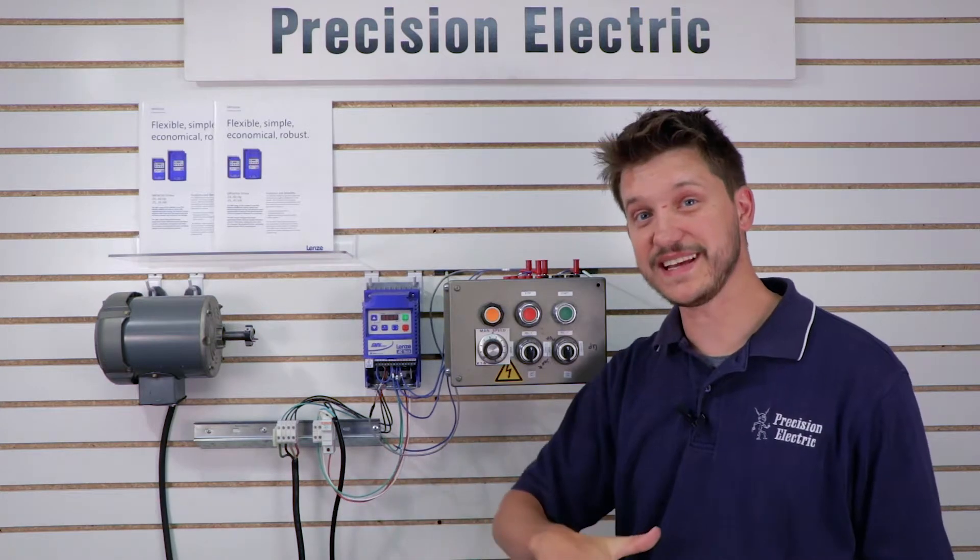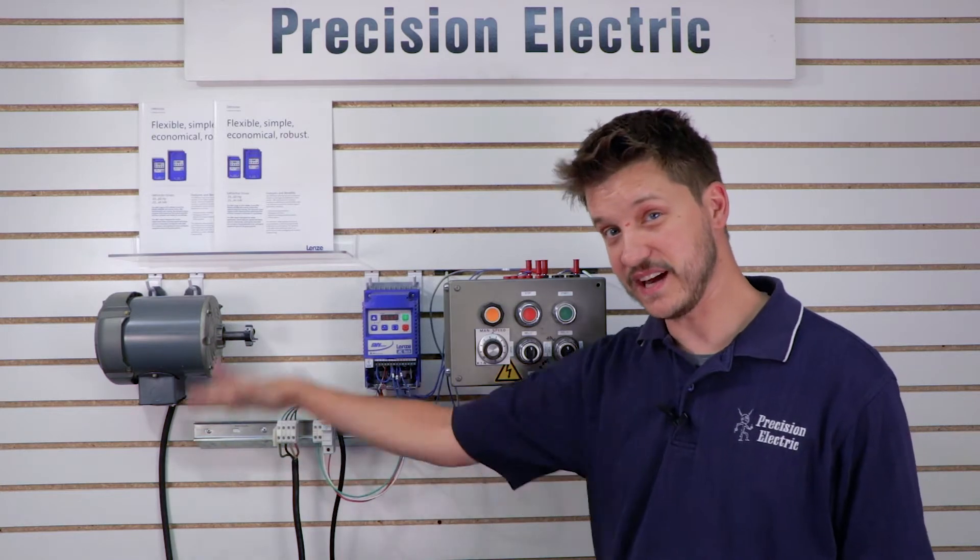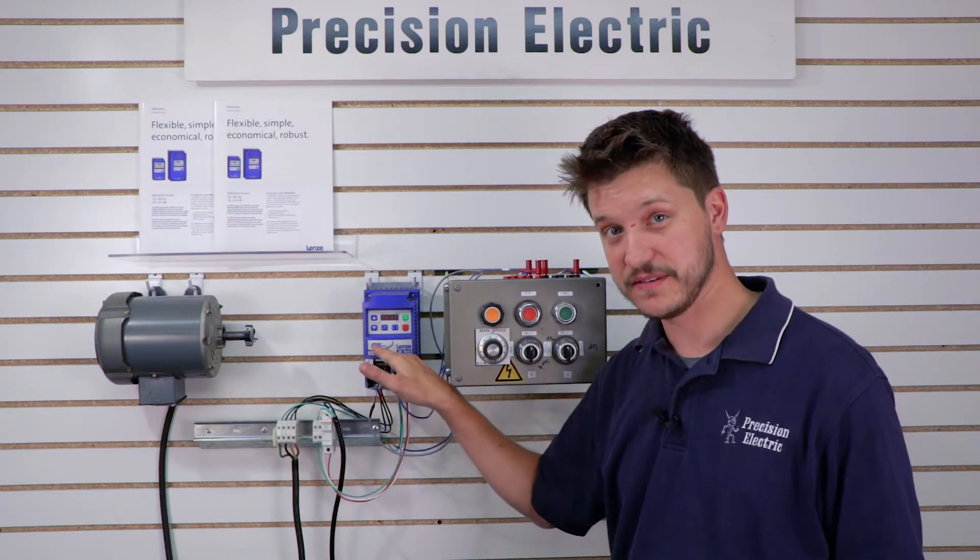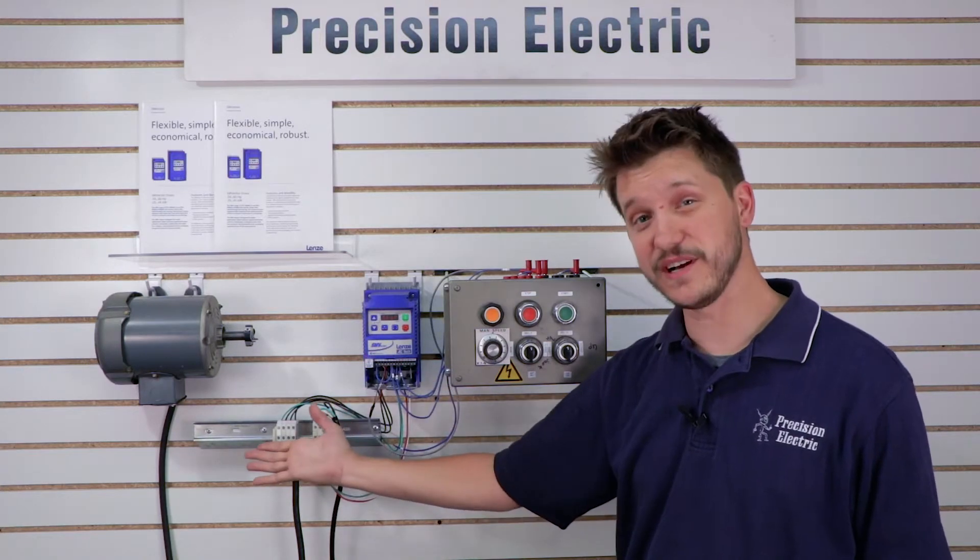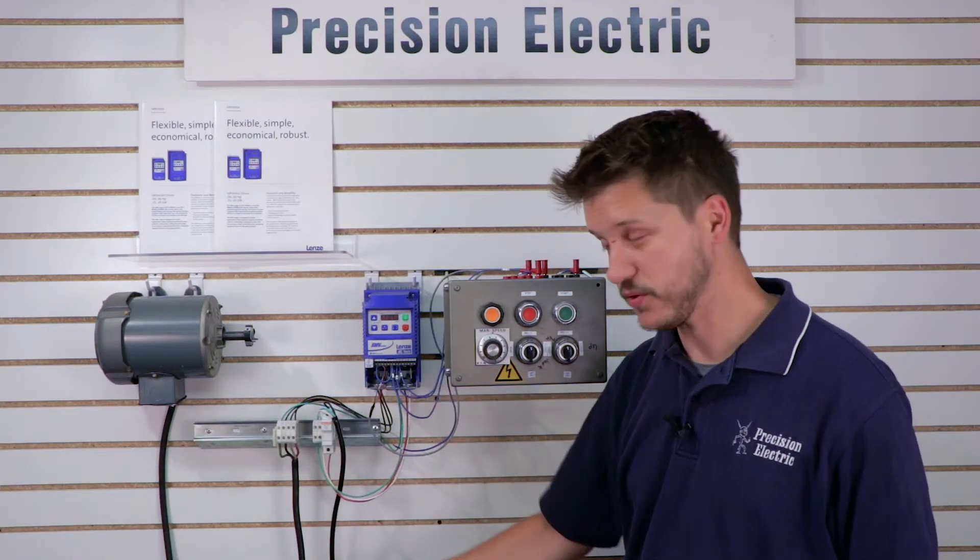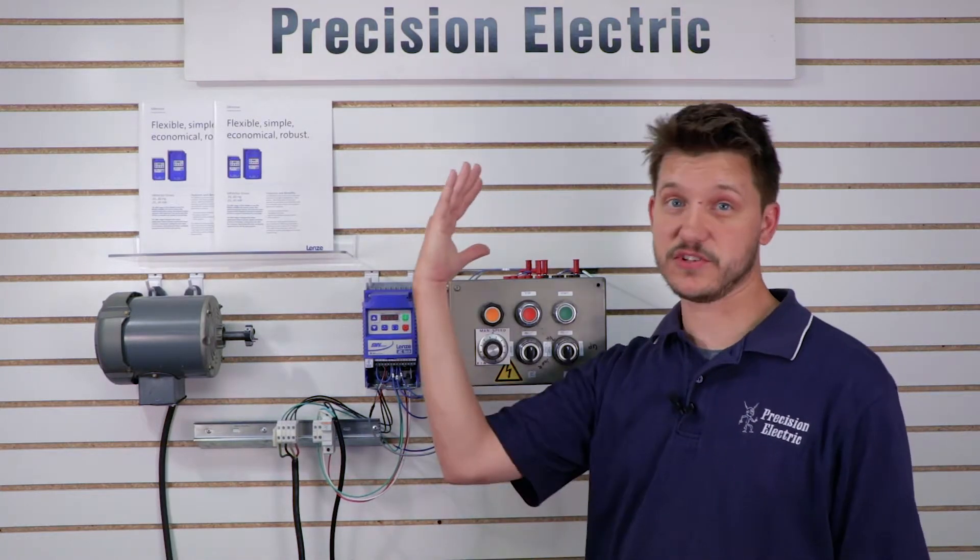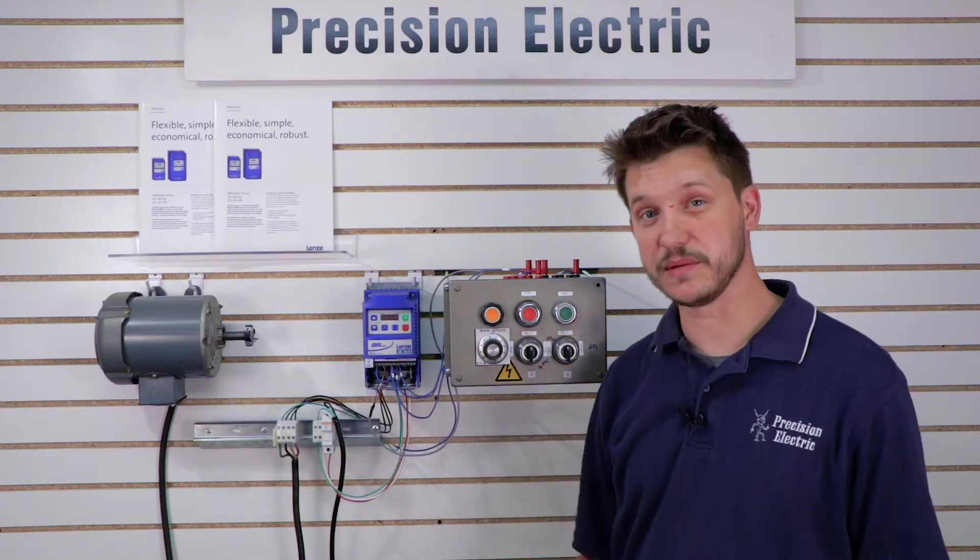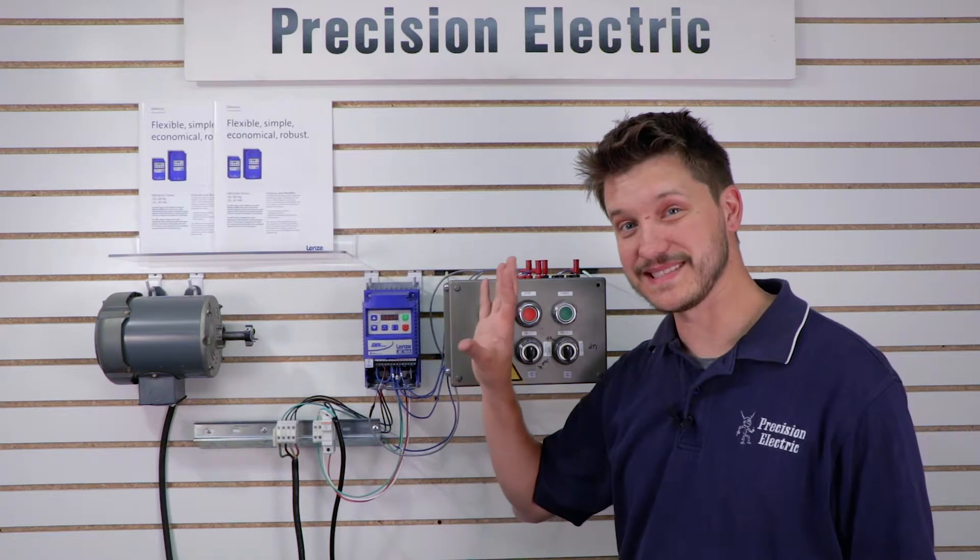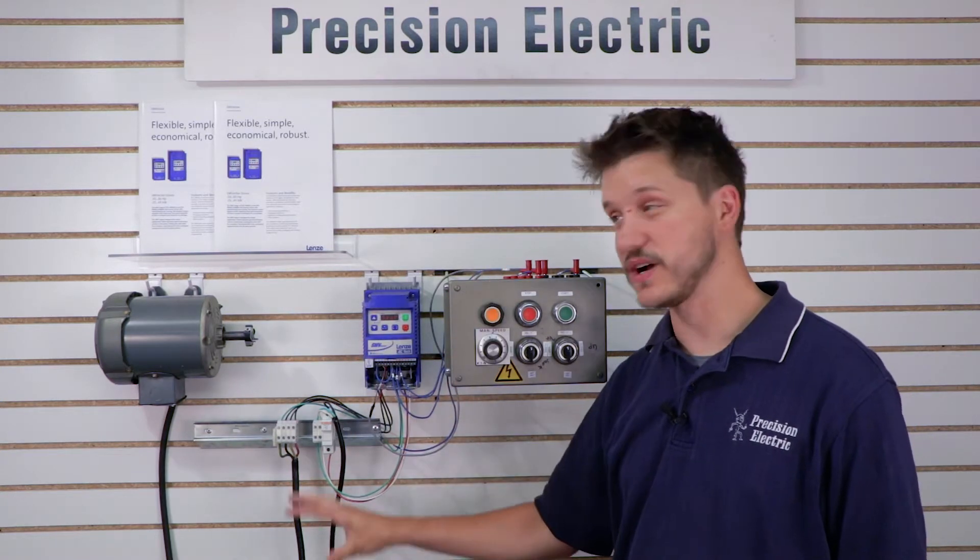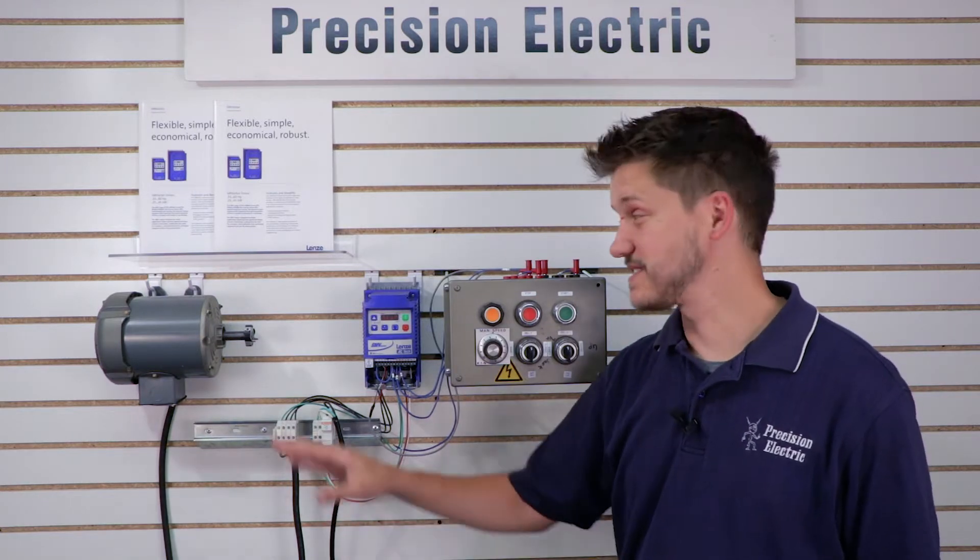In other words, nothing that can disconnect the output power from the drive to the motor. That is a guaranteed way to blow up your drive, probably not your motor, but it's a guaranteed way to blow up your drive. Because if for any reason that opens up, the power that's flowing through the drive to the motor has to go somewhere and it gets pushed back up into the drive. That's how people commonly blow up the output section of their drive when they call. So you have to have a single connection from the output of the drive to the motor.